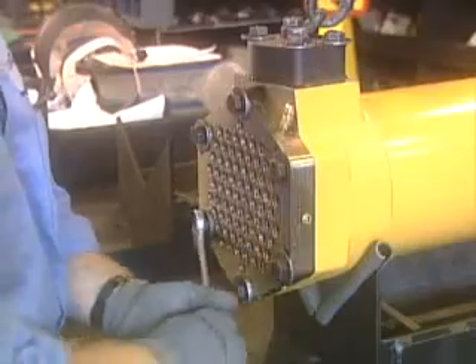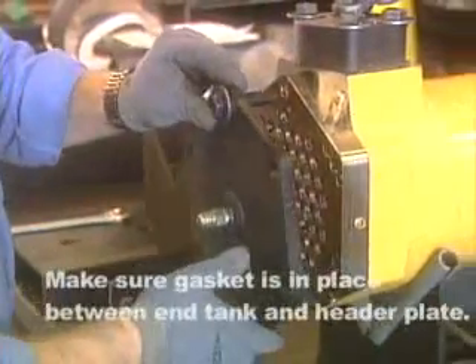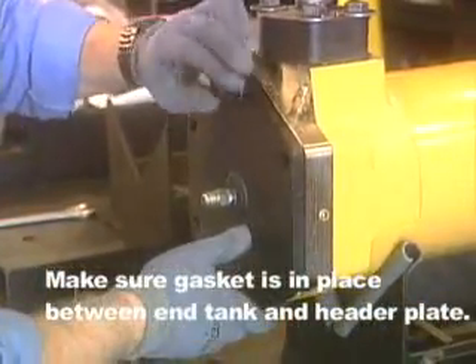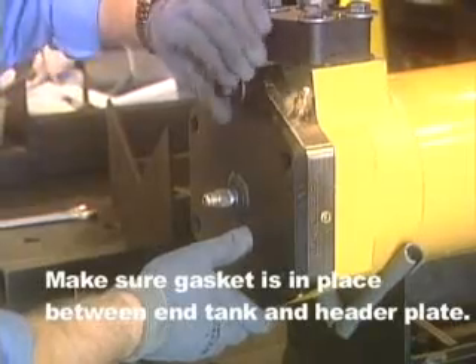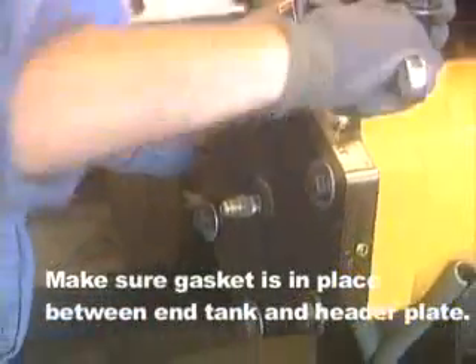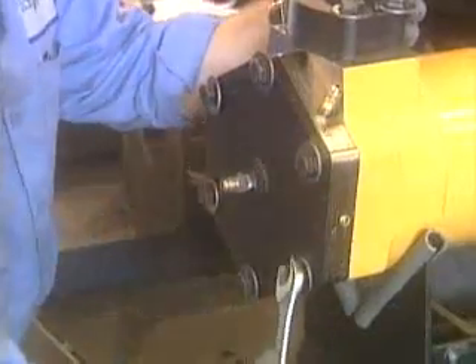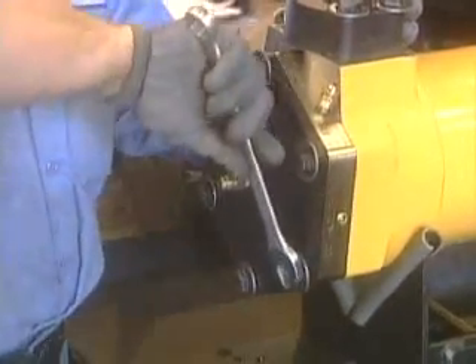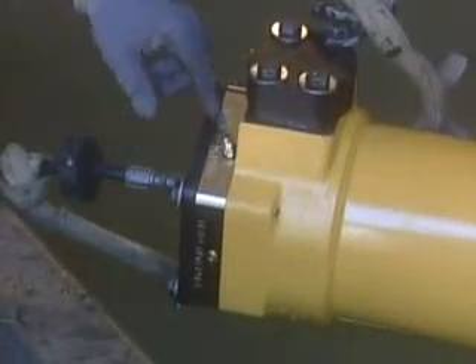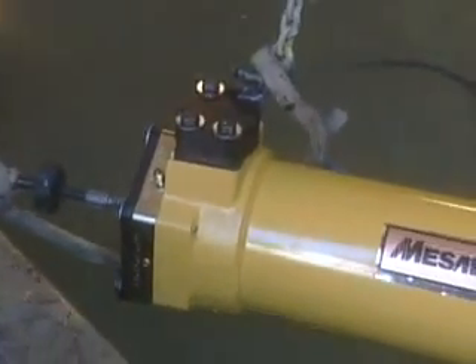To test the tube side, typically the water side, follow the pressure cycle steps in the System Protector Service Manual. Remove all flange bolts. Install appropriate test plates to both ends of the cooler using appropriate length bolts. End tanks may be used for this purpose. Install and torque all flange bolts to proper bolt specification. Begin the sequence of pressure cycles as stated in the System Protector Service Manual.